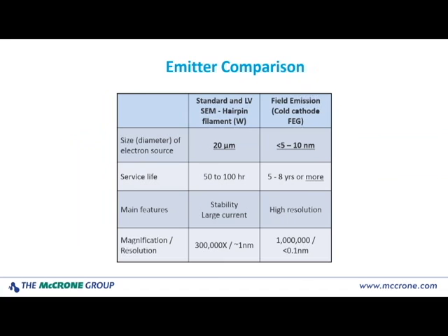The tungsten filament is about 120 micrometers in diameter, but the area that's going to be producing the electron beam is only 20 micrometers in diameter — that's going to be the diameter of the cloud or beam of electrons being emitted. If you go to the field emission gun, it is considerably smaller; we're talking about an area on the tip that is less than 5 nanometers in size. So with the smaller diameter beam at the gun, we can keep it finely focused, and when we get to the sample, we can get fantastic resolution because it is super small. The magnifications available on standard type SEMs and LaB6 is up to about 300,000x, achievable at maybe a nanometer resolution — only if you have everything perfectly aligned and the world's best prepared sample. So you might really anticipate getting something more on the order of 25,000 to 75,000x in most cases.